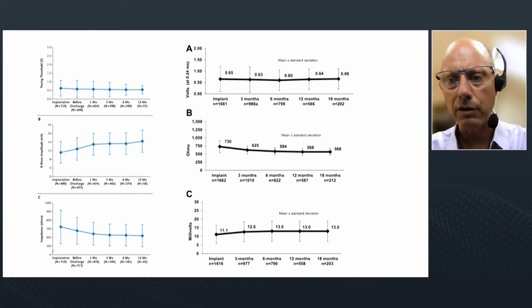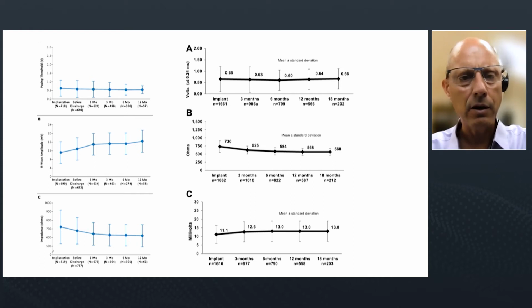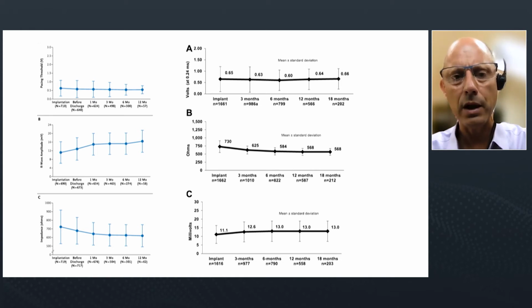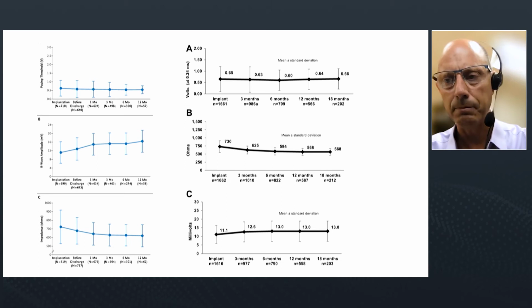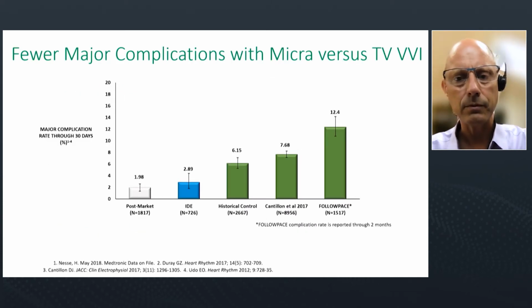The electrical characteristics of the Micra device have been remarkably consistent. So we can see, looking at pacing thresholds in these 2 studies and going out to 18 months on the right-hand side, the pacing thresholds are very low. And that's particularly important as the pulse width is 0.24 milliseconds compared to traditional transvenous devices where the default is 0.4 milliseconds. And we can see sensing, if anything, improves with time, and impedances are stable.